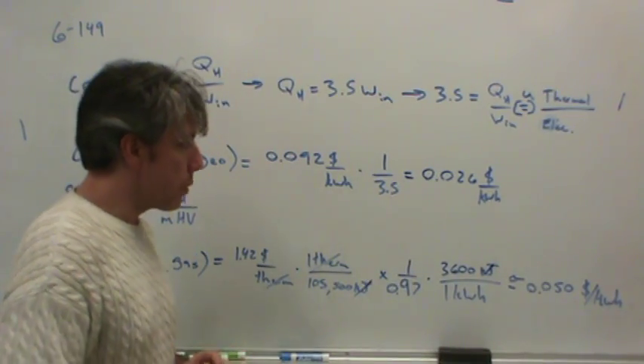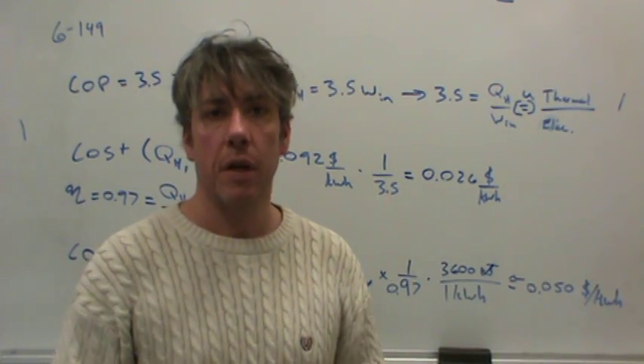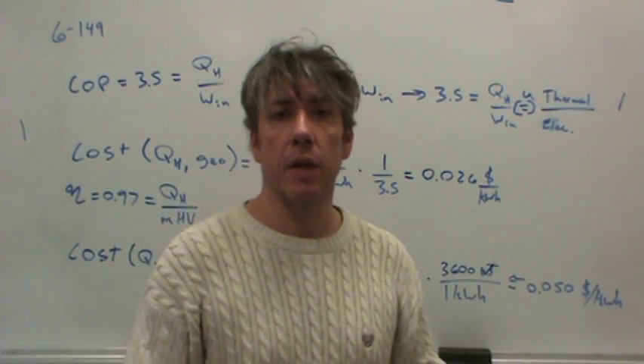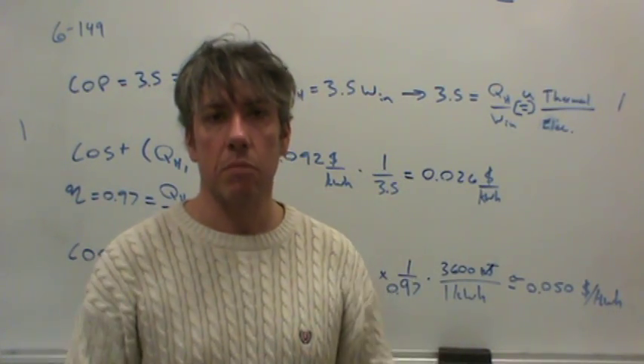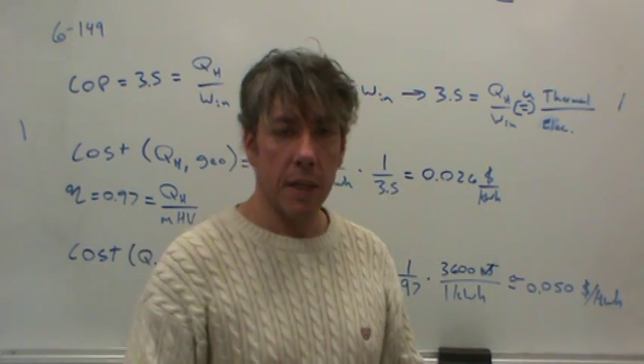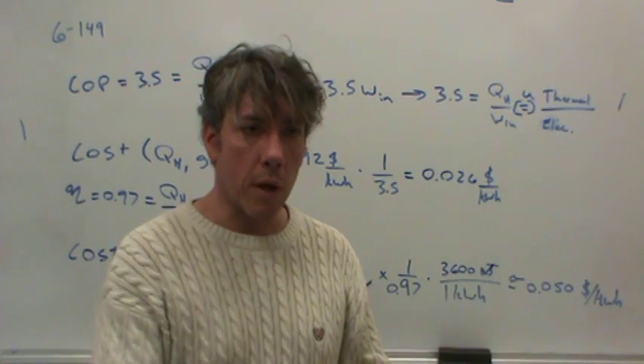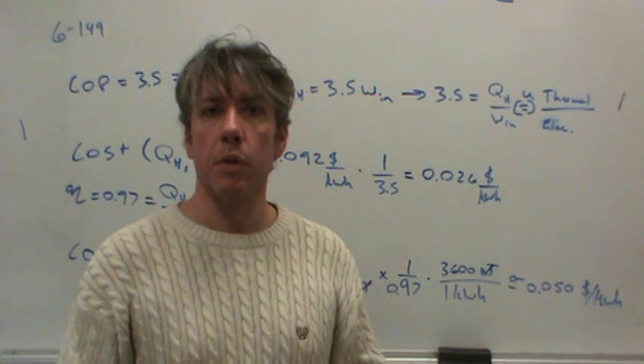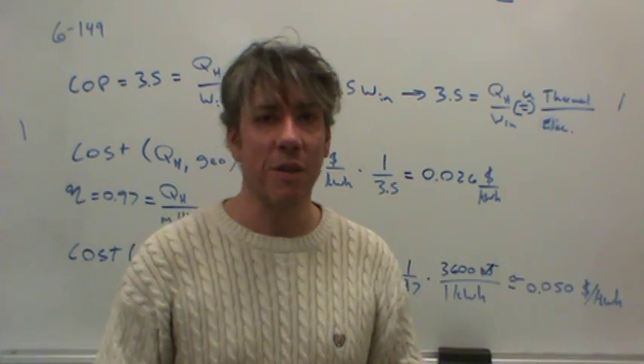So geothermal is a great thing. The reason it's not everywhere is because it costs quite a bit of money to essentially put a heat exchanger in the ground, because all you're really doing is exchanging heat with the ground. In the case of the Galt House system, they're using a well system. And what that means is they drill down into an aquifer and pump up water that's at an average temperature year-round, and you either extract thermal energy from that water or dump thermal energy into that water. And I'm sure they have some problems with the fact that water from an aquifer like that is going to have a lot of mineral content, and you're going to have trouble with corrosion. But at $20,000 a month, that's a lot of maintenance budget, so it can be practical.